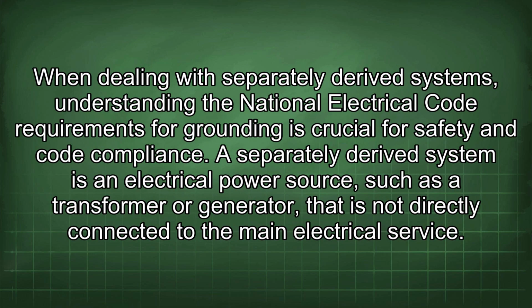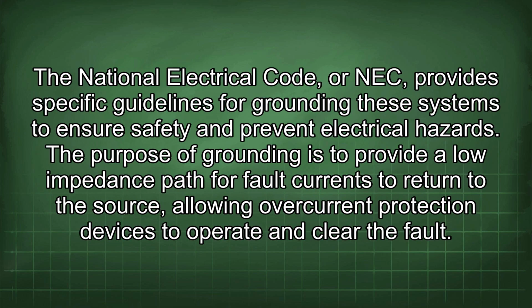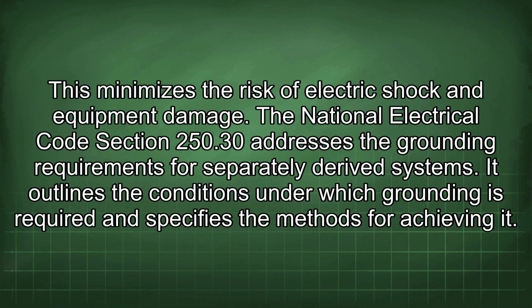When dealing with separately derived systems, understanding the National Electrical Code requirements for grounding is crucial for safety and code compliance. A separately derived system is an electrical power source, such as a transformer or generator, that is not directly connected to the main electrical service. The National Electrical Code, or NEC, provides specific guidelines for grounding these systems to ensure safety and prevent electrical hazards. The purpose of grounding is to provide a low impedance path for fault currents to return to the source, allowing overcurrent protection devices to operate and clear the fault. This minimizes the risk of electric shock and equipment damage.